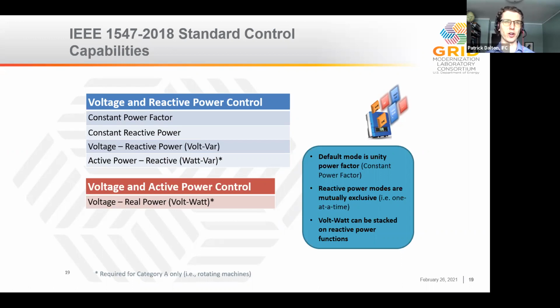Thinking back a few slides to that consuming reactive power, the VAR draw, there are four different ways, four different controls, to do that. And then there's one for reducing energy production. We can only enable one reactive power mode at a time, but we can stack the active power, or the volt-watt function, on top of that. We'll look at that in one of the next slides.